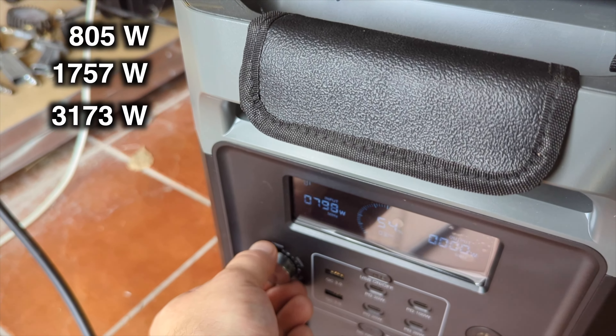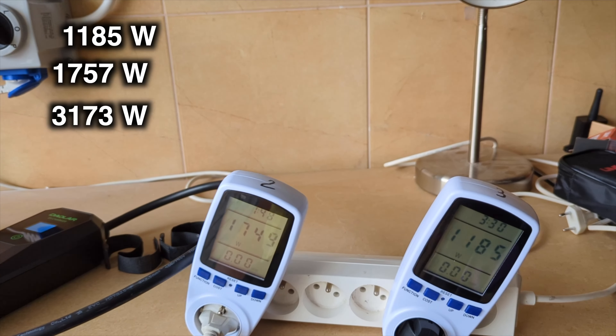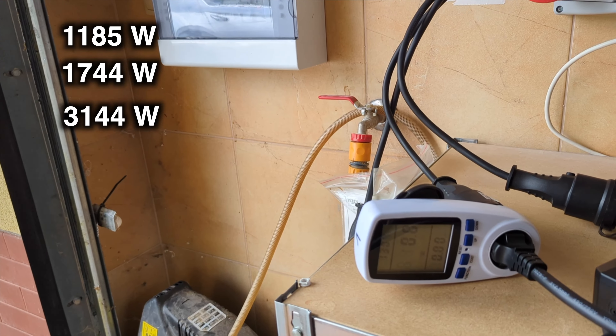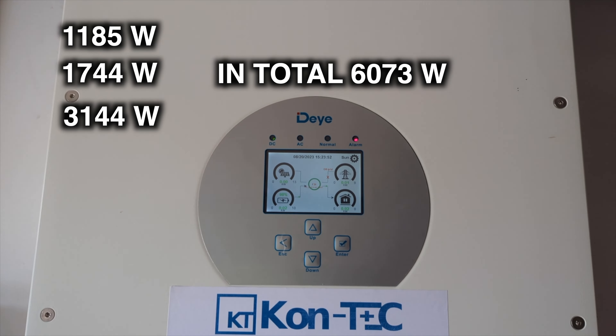I'm increasing the energy consumption to 1200 watts: 1185 plus 1744 plus 3144 watts. In total 6073 watts, and the inverter has now shut off. Overload. We now know the maximum load the inverter can handle on a single phase.